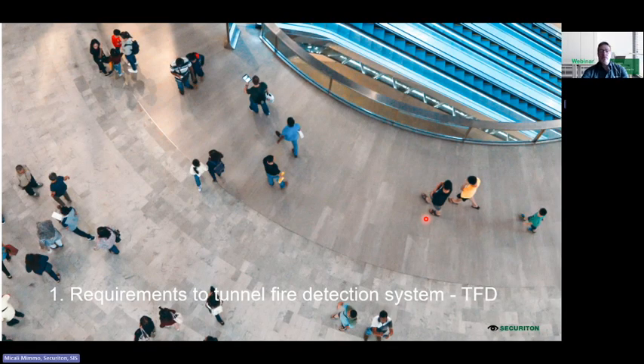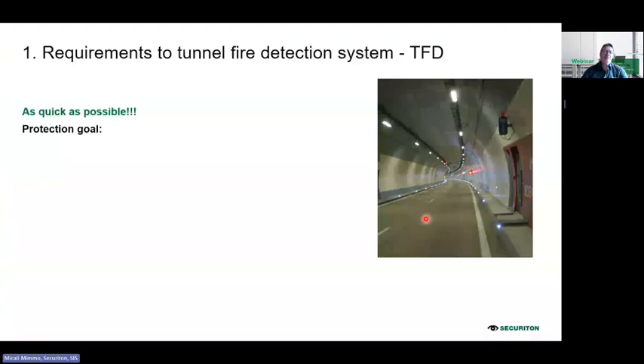Well, let's start with the requirements of a tunnel fire detection, what is needed for this kind of application. Normally, when we talk about fire detection in a road tunnel, it is always as quick as possible. The system must react very quickly because we know the risk in a tunnel. Of course, the protection goal is first of all personal security. Always when we talk about fire detection systems, personal security is the first priority. And then of course we also have the infrastructure protection. This is also important in a tunnel. The faster we can detect, the faster we can control the fire, and probably we will have less damage in a tunnel if everything works well.